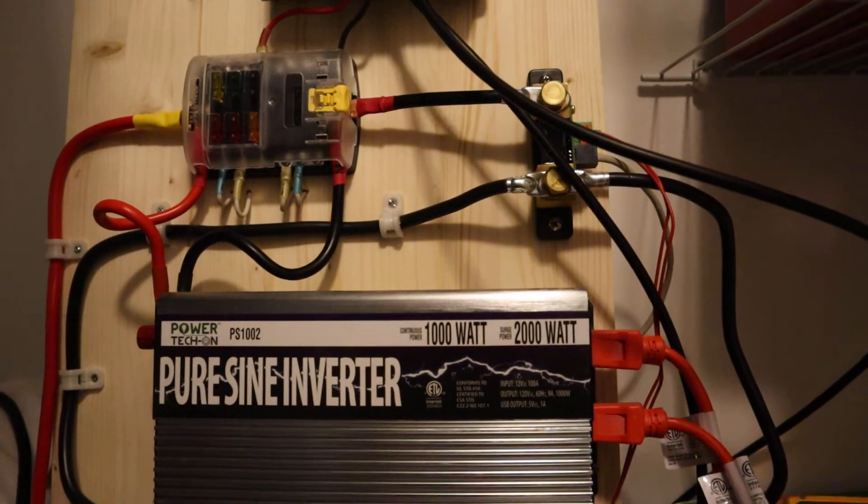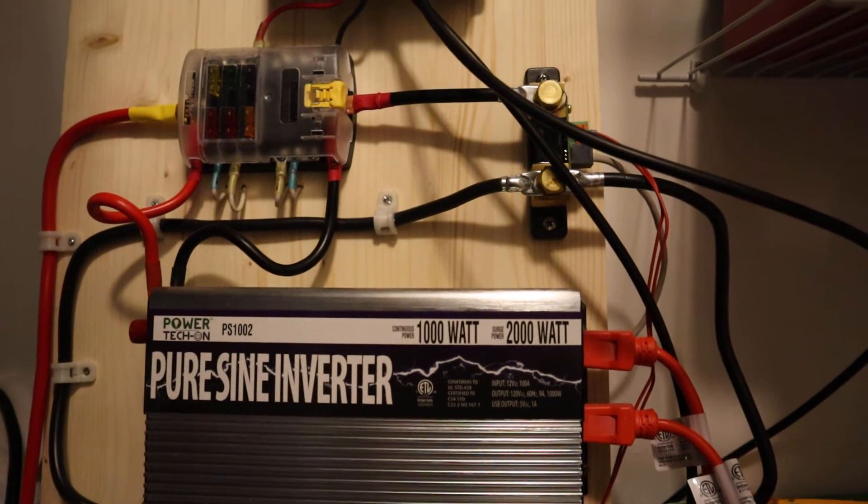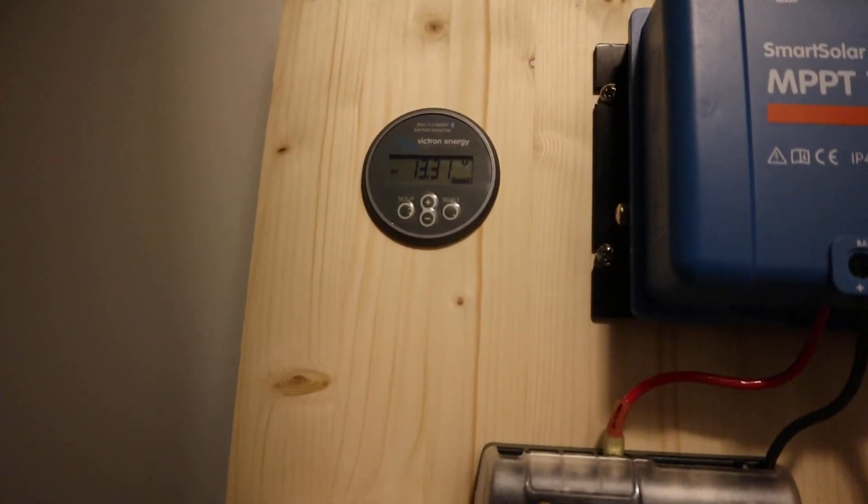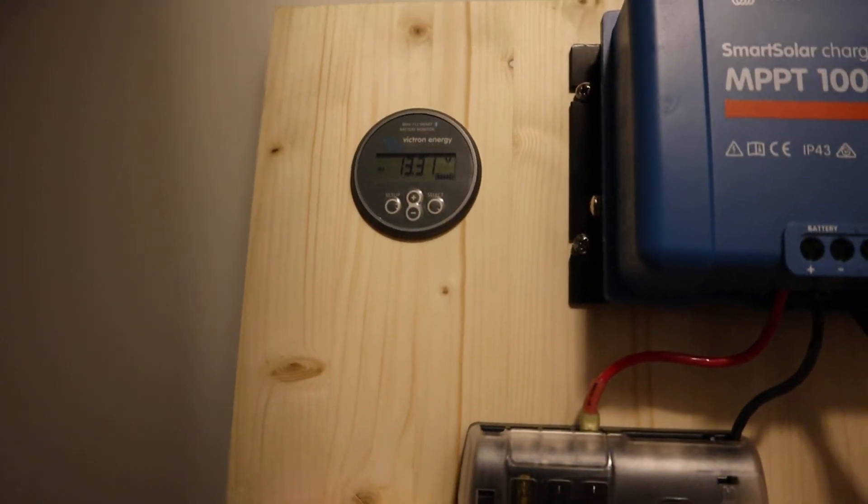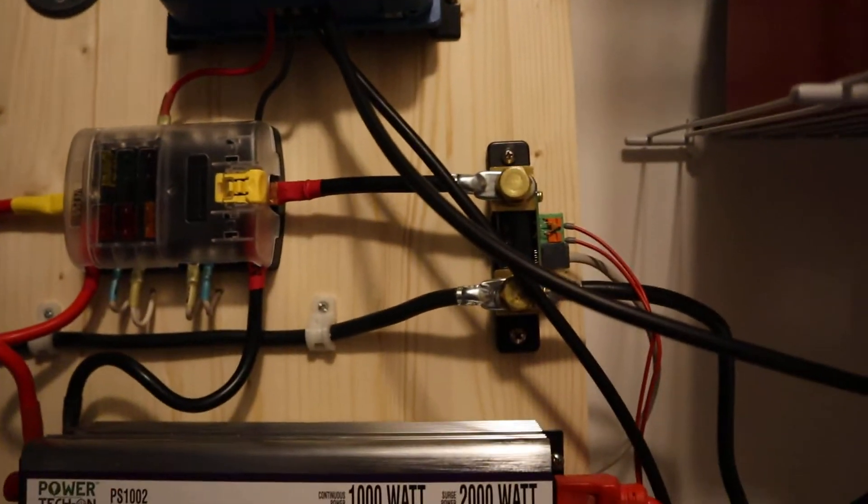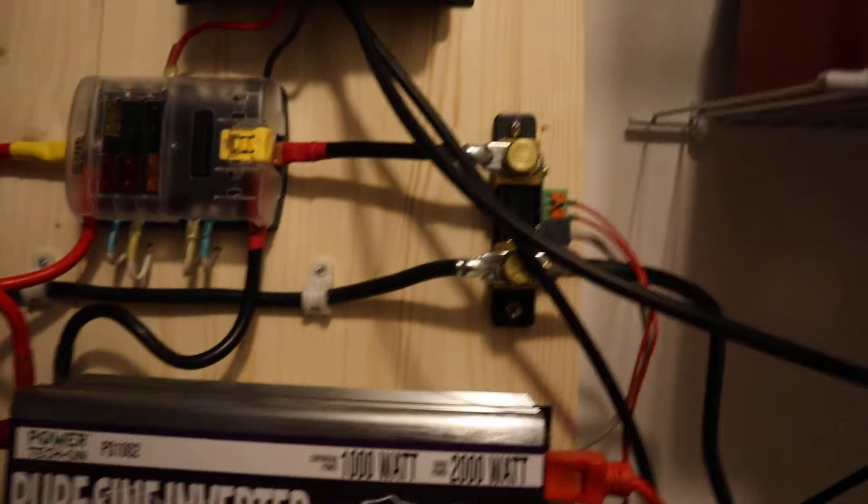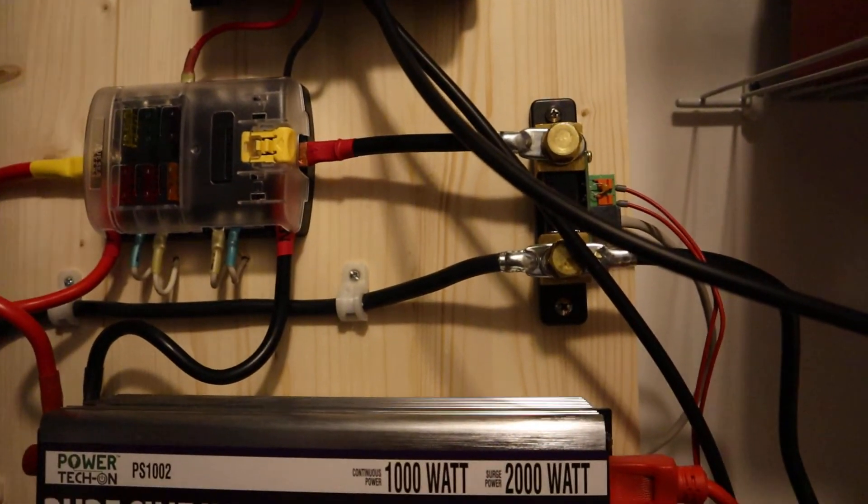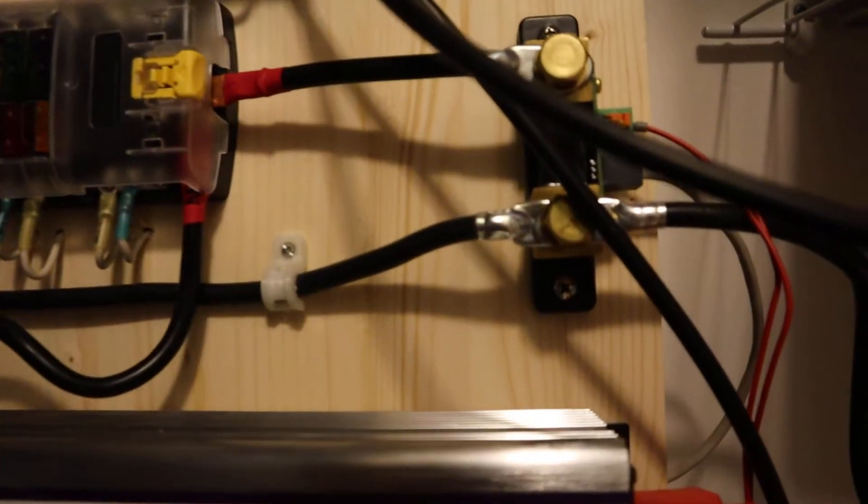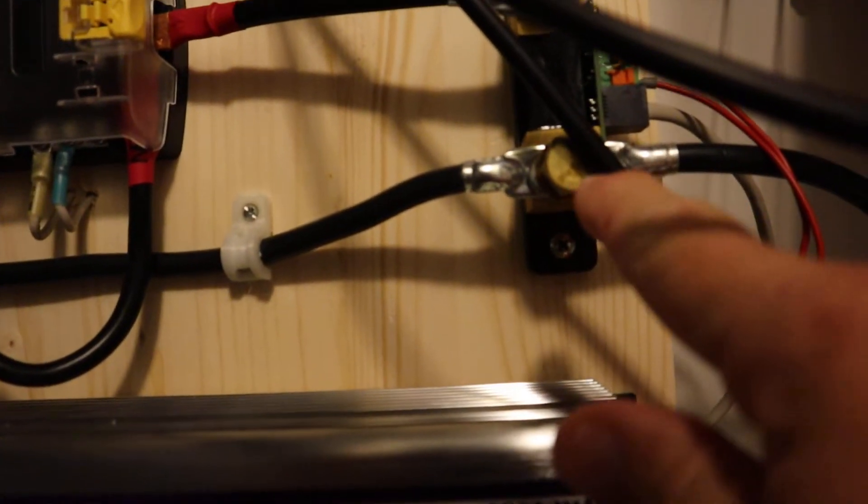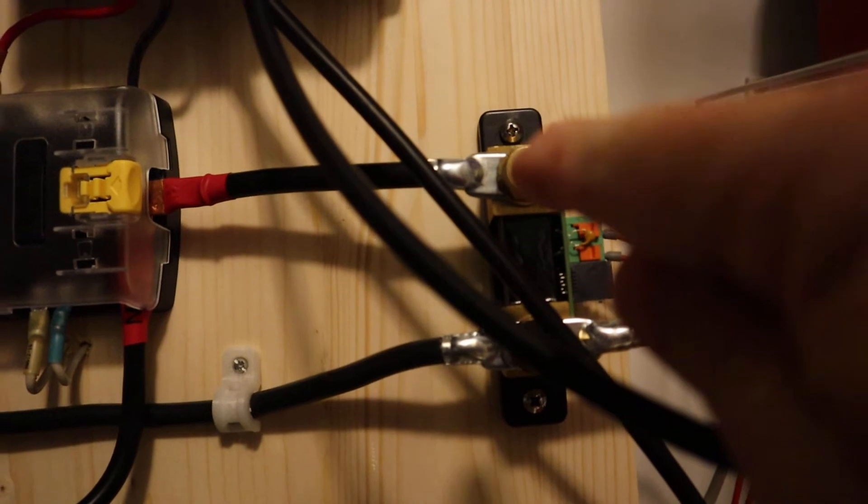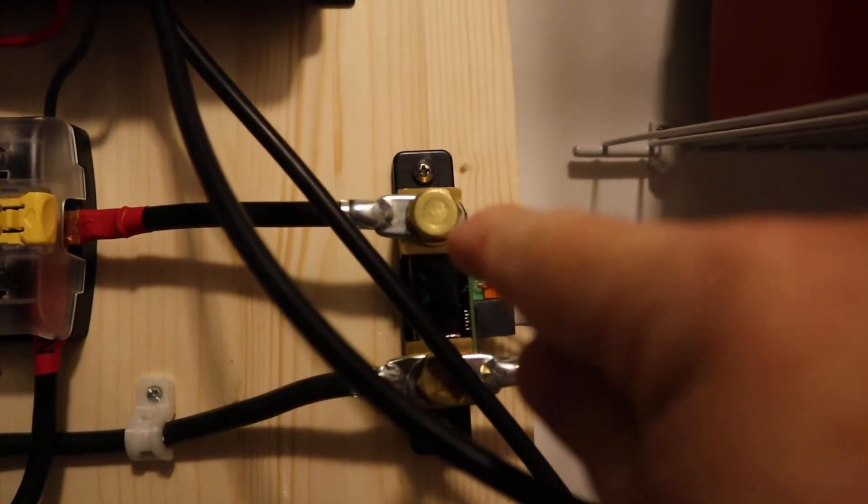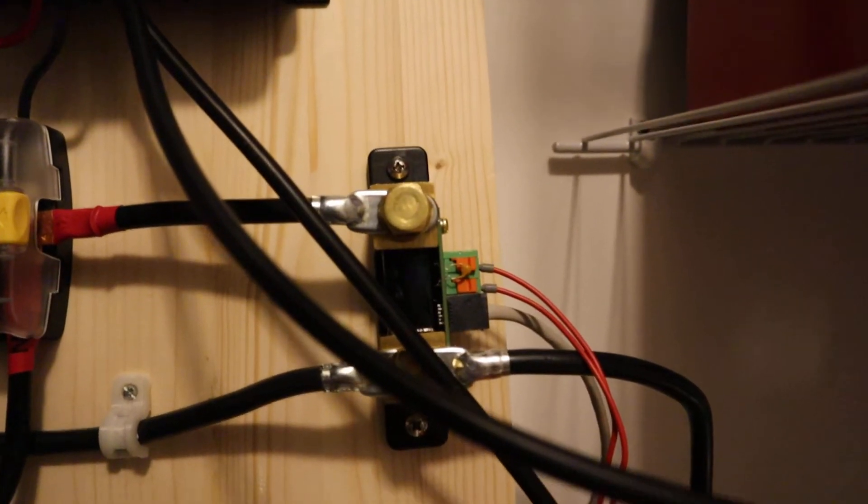I'm going to do a quick discussion on how to calibrate the Victron BMV 712 battery monitor with your system. Basically you do a zero calibration. This is the battery side of the shunt and this is the load side. So what you're going to do is remove this screw and lift this wire off.